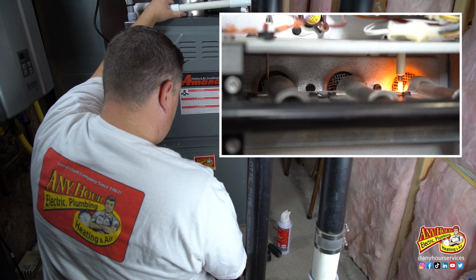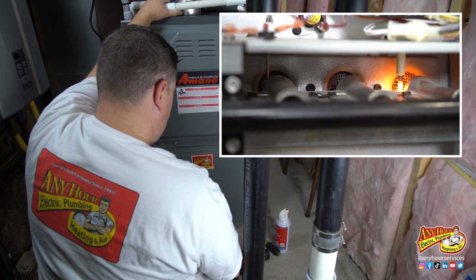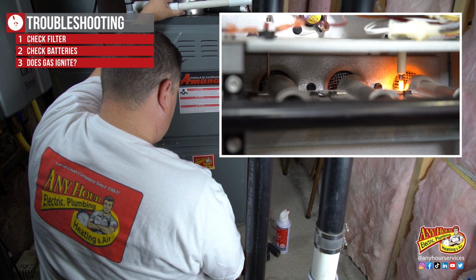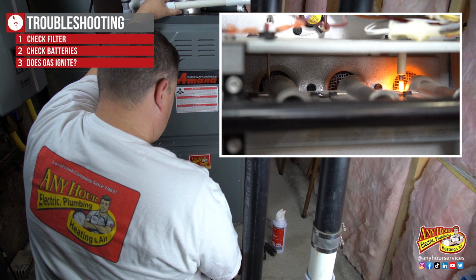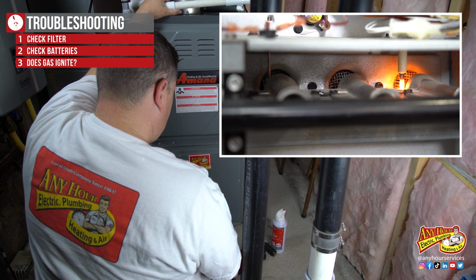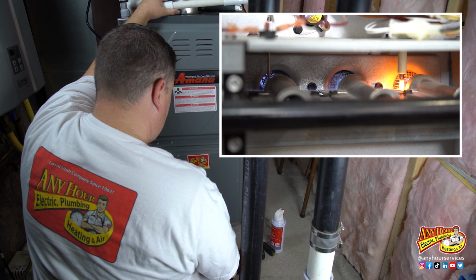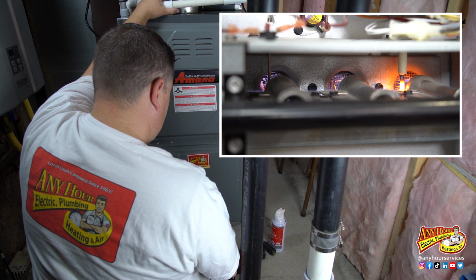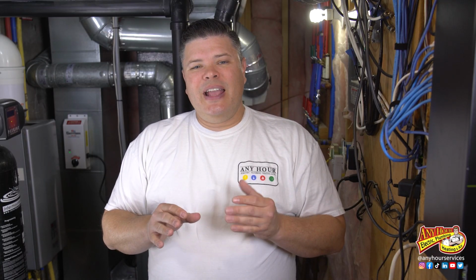So go to wherever your furnace is and listen for it to turn on. You should hear the gas ignite. It'll sound like little jet engines. If you hear the gas ignite and then turn off pretty quickly, the flame sensor might not actually be registering the flame.